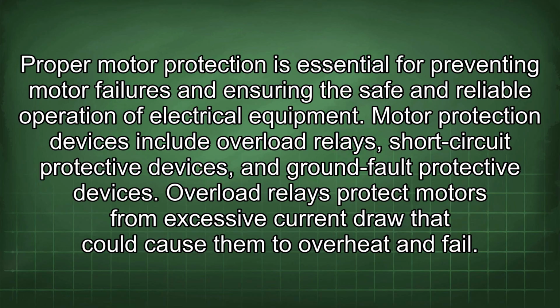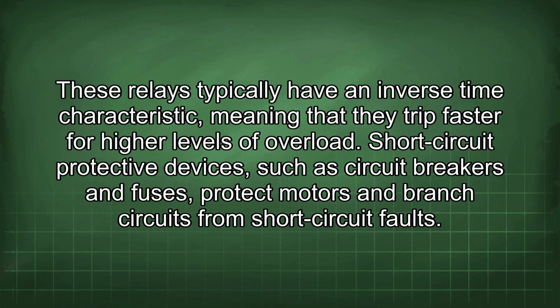Motor protection devices include overload relays, short-circuit protective devices, and ground fault protective devices. Overload relays protect motors from excessive current draw that could cause them to overheat and fail. These relays typically have an inverse time characteristic, meaning that they trip faster for higher levels of overload.